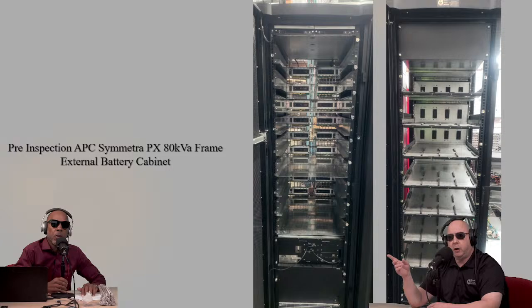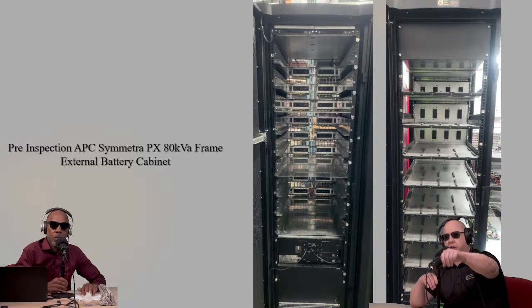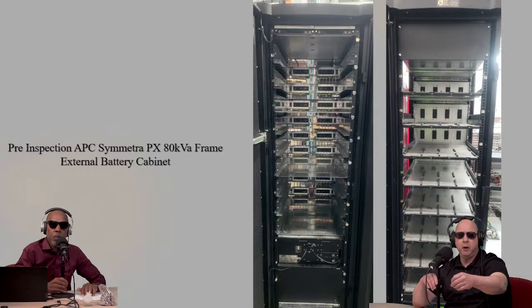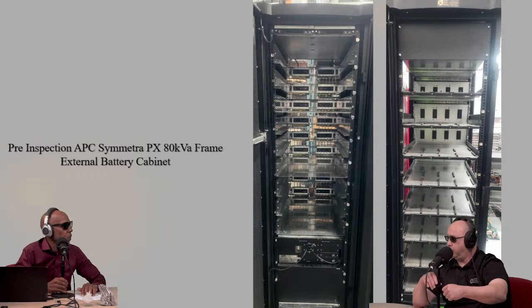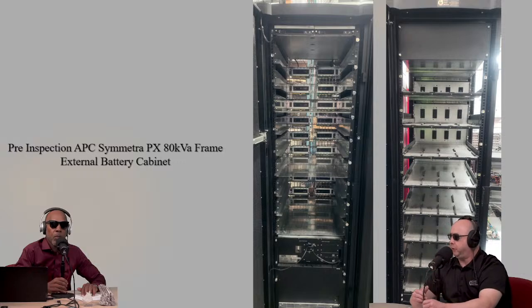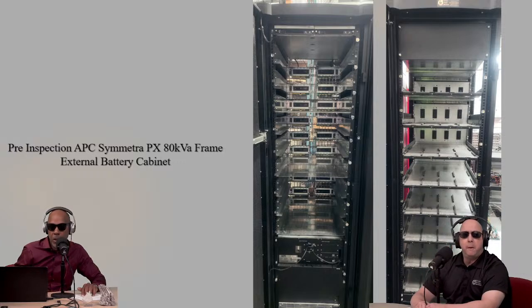On the other side is a battery cabinet, same thing, we're looking at the connectors and wiping down. If you see those black plastic pieces, those are guides for the battery module to slide in. If one's broken or a screw is missing, we'll replace the guide and the screw hardware, because that's part of refurbishment. A broken piece is a broken piece, you replace it. If it's missing a screw, you put everything back. We do the same thing with the battery cabinet too.